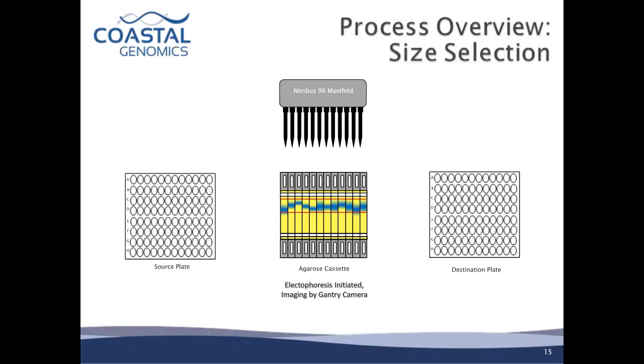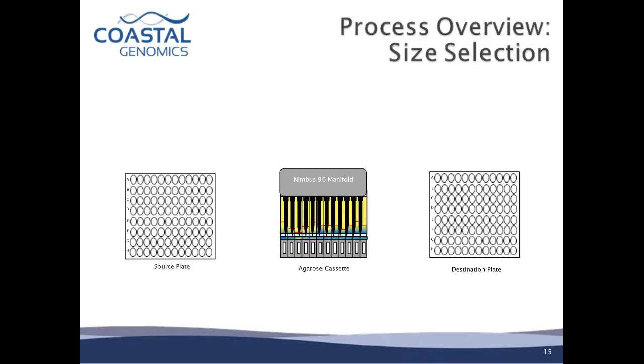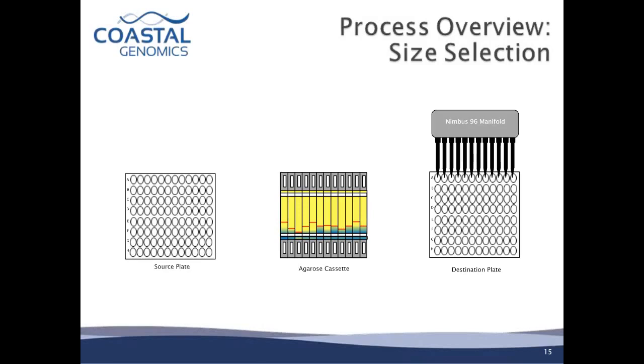Once every couple of minutes a picture is captured, and the software measures the mobility of the DNA sample in every channel and identifies where the target is in each channel — since the target is not necessarily the same in every channel. The software then alters the voltage to manipulate mobility in a way that allows synchronous arrival of target fractions at the downstream extraction well, at which point the manifold aspirates the sample into a destination plate for further processing.